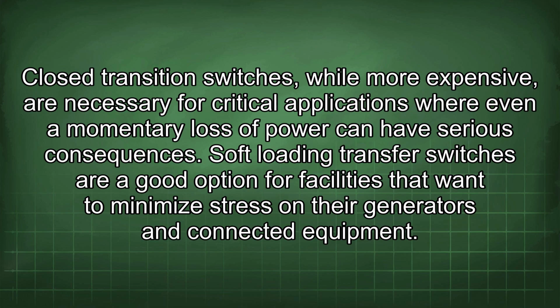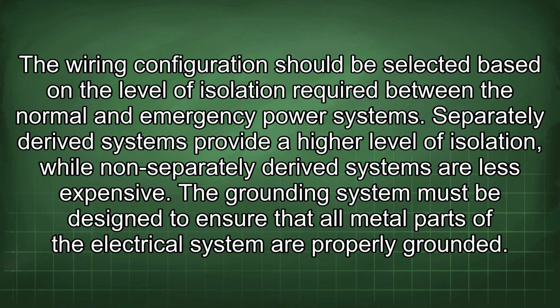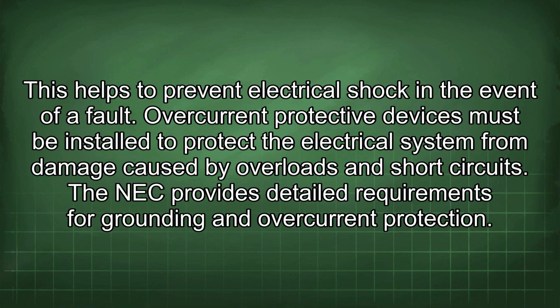The wiring configuration should be selected based on the level of isolation required between the normal and emergency power systems. Separately derived systems provide a higher level of isolation, while non-separately derived systems are less expensive. The grounding system must be designed to ensure that all metal parts of the electrical system are properly grounded. This helps to prevent electrical shock in the event of a fault.